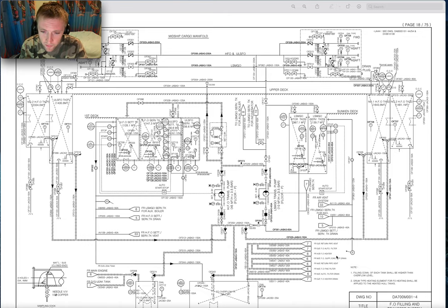So we can see also here all this piping, there is a lot of piping coming here and falling down to one common line and going to the overflow tank. Also our overflow tank has temperature indication, has a level switch for the high alarm. So this alarm must also be tested, and it's very, very important for testing. Also the adjustment of the alarm is really, really important.